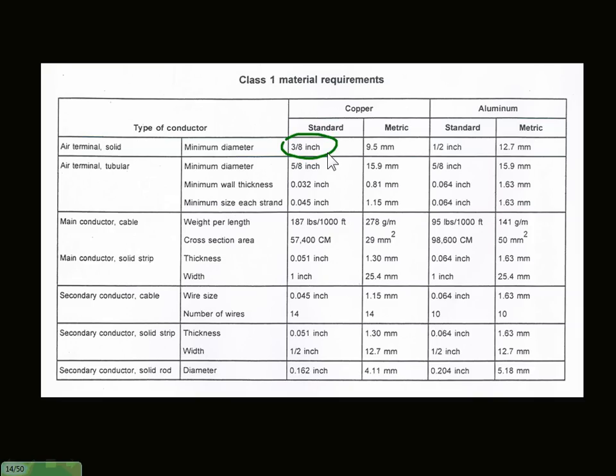So 3/8 of an inch is the minimum material size for an air terminal. Which this is actually 5/8. So this one's a little bit bigger than the smallest one. The reason for that is lightning is hot and it is very powerful. If you go any thinner than this, what happens is when lightning strikes this, it can actually melt this. And if the cable is smaller than this, it can actually melt the cable as well.